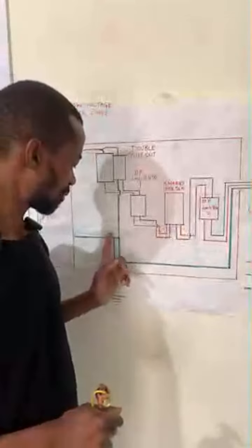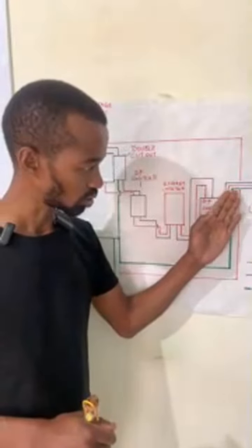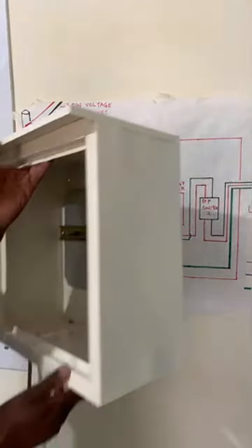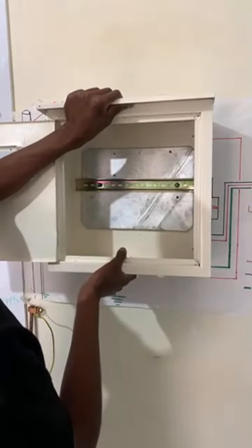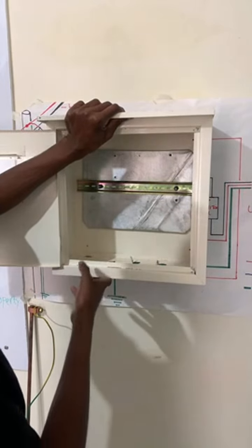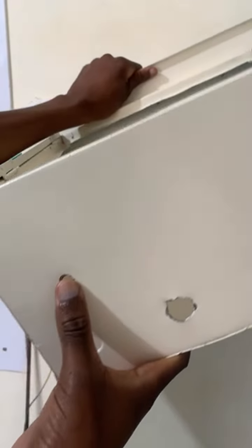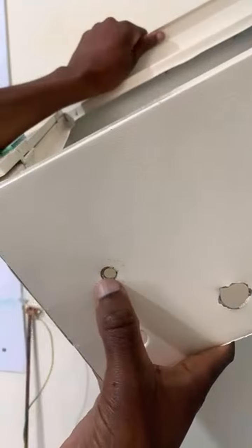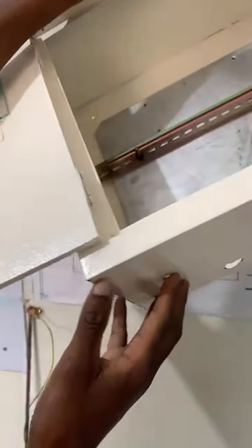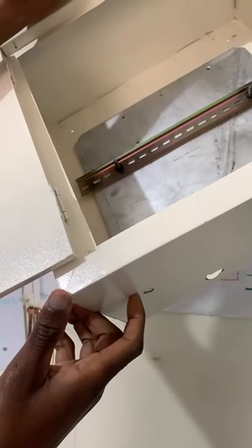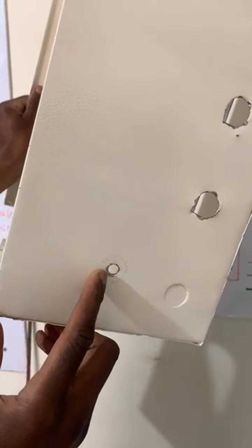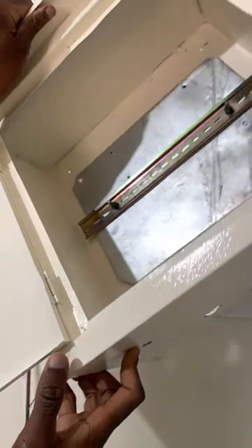So at this point here, we now have our earthing going all the way to the consumer unit. But before we go far to the consumer unit, let me just touch on these parts of the meter box that make it a very important point for earthing. At the meter box, you will then create a point whereby you can connect the earthing. For instance, at this point, you can make a connection there. You can use a bolt as well as a nut and ensure that you tighten your earth there so that the entire meter box is generally earthed, all right?